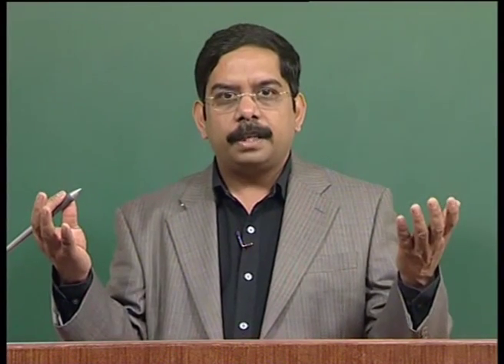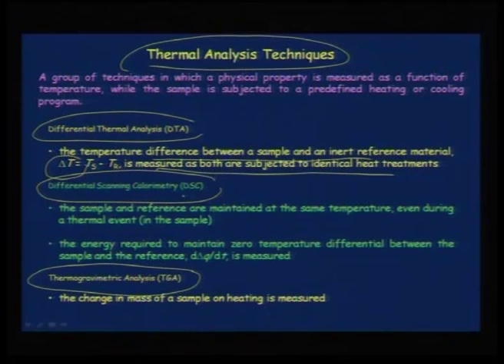The reference material must be inert to the temperature program — stable with no physical or chemical changes. Whatever difference exists between the reference and sample is solely the manifestation of the sample. In differential scanning calorimetry, we are not measuring the temperature difference between sample and reference; instead, we maintain the same temperature for both, and if the sample undergoes a heat-releasing or heat-absorbing reaction, the heat flow is recorded.